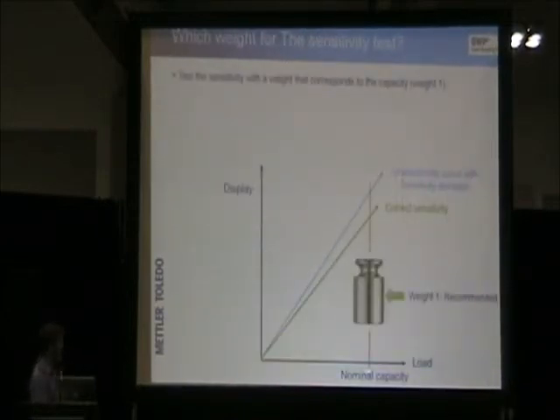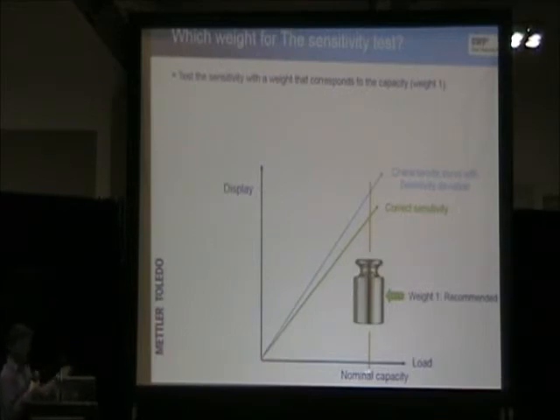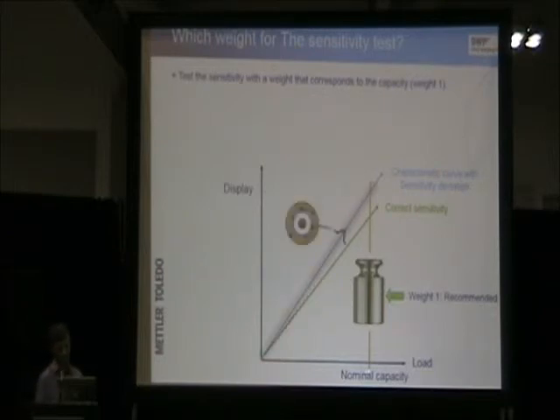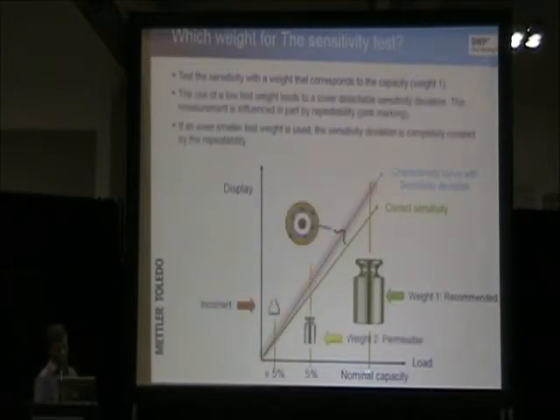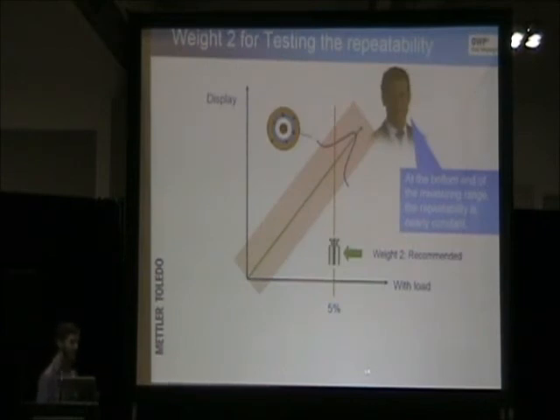So again, as I stated before, because sensitivity is furthest apart near your capacity, you want to use a test weight as close to capacity as possible. Because if you start to do testing at the low end, near where you're weighing your samples or the sample mass, you're not going to be able to actually see if the uncertainty itself is being shown during your testing.